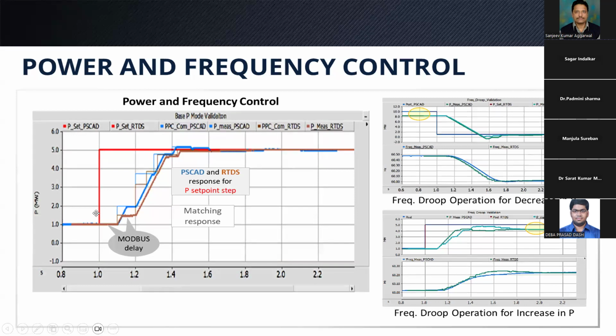So here, not everything is updated instantaneously. We see ramps like a staircase in the output of the PPC and the input of the PPC because it's using a communication protocol. So values are not updated instantaneously, but they have a delay, and so it appears like a step. To match the two responses, the PSCAD model should also be made capable of modeling this Modbus delay.